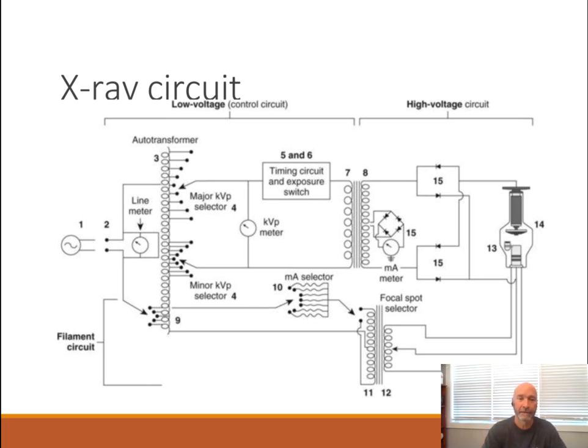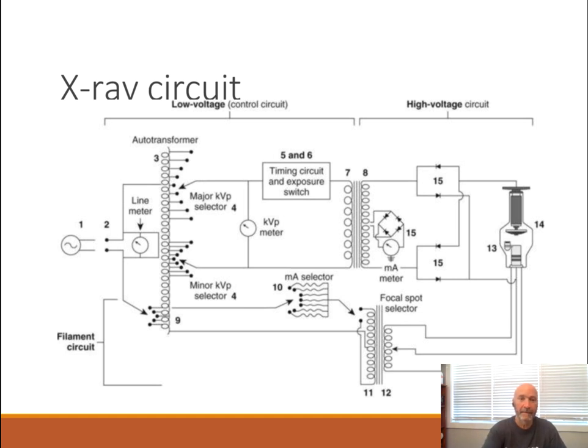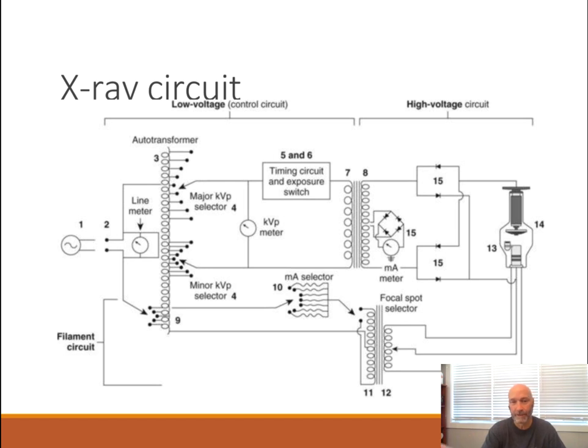I usually start this part of the lecture by saying the first thing that the electricity gets to is what we refer to as an autotransformer. An autotransformer is a form of rheostat. We've got a couple of different rheostats — there's also a rheostat down here in the filament circuit. What a rheostat does is it's kind of like a dimmer switch on a light — you can make it brighter or dimmer. This is basically our KVP selector. We supply alternating current to it, meaning electricity goes in one direction and then back in the opposite direction. We have to have alternating current to make this thing work.